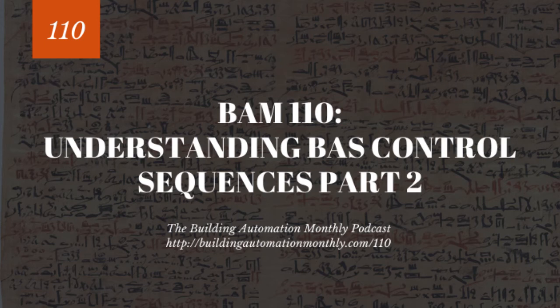It's horribly difficult to control. Anyways, that's neither here nor there. So in this case, in this sequence, it's hot water. It's a reheat valve. So first thing, we need to make sure we have a proportional valve actuator, because controlling with floating or with incremental, whatever you want to call it, actuators, it's just a pain in the butt. Let's control with proportional, give ourselves greater accuracy, not have to worry about the stroke time and all that fun stuff.